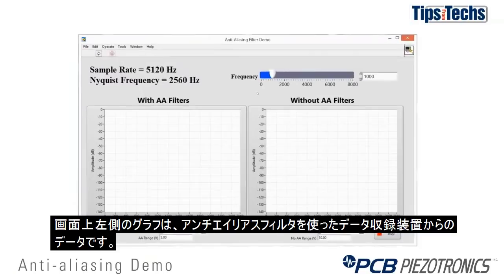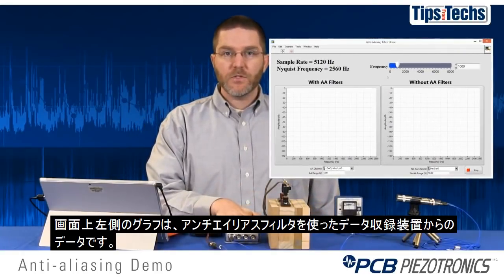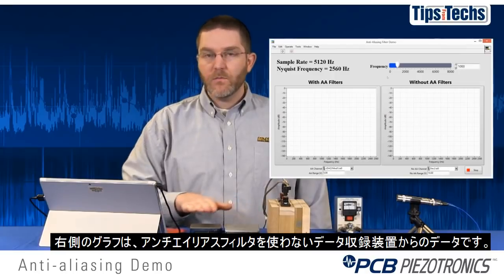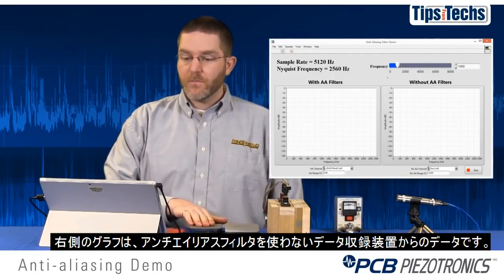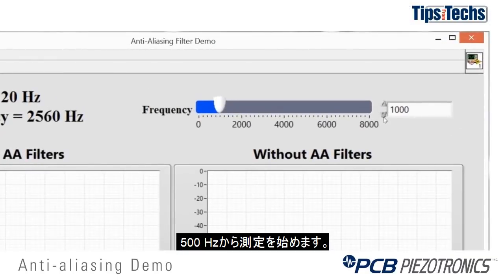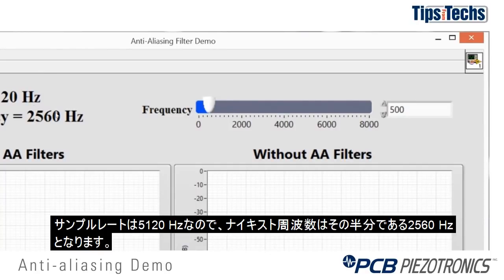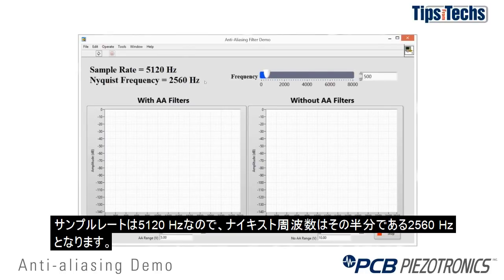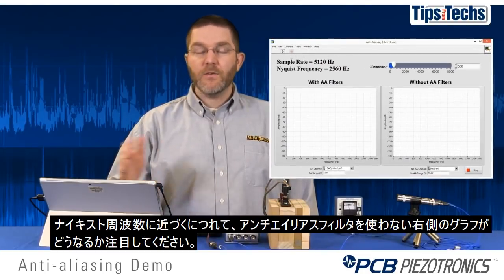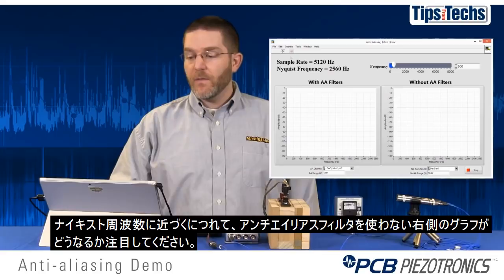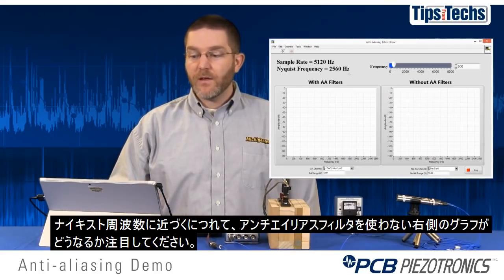Now we'll start the demo. On the screen you'll see on the left-hand side the plot with data from the anti-aliasing filter data acquisition system, and on the right-hand side will be data without the anti-aliasing filter. We will start at a frequency of 500 Hz and increase by increments of 250 Hz. The sample rate is 5120 Hz, which makes our Nyquist frequency half that, or 2560 Hz. As we approach that Nyquist frequency, watch what happens in the plot on the right-hand side without the anti-aliasing filters.